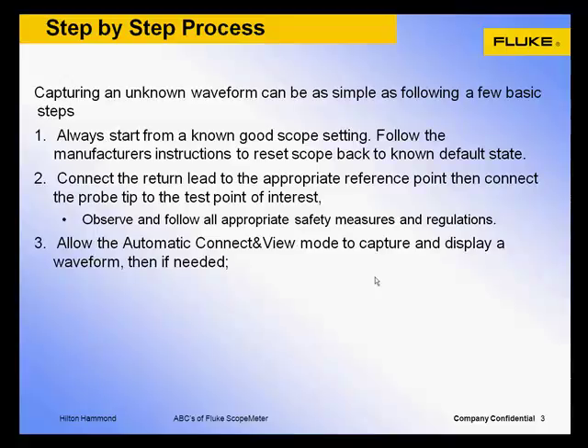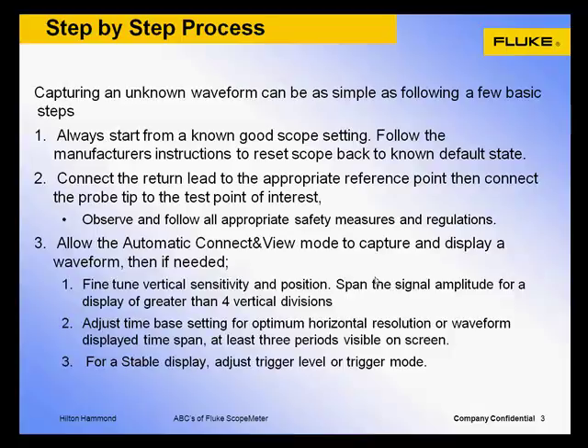Once you have a good starting point, you can fine tune the settings to best capture or analyze specific parts of the waveform. Start by fine tuning the vertical sensitivity and position, spanning the signal amplitude for a display of greater than four vertical divisions. Next, adjust the time base setting for optimum horizontal resolution or waveform display time span. For automatic measurements, make sure you have at least three periods visible on screen.